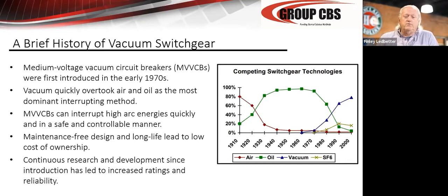Vacuum breakers quickly overtook all the other medias, or, you know, oil, gas, and air. Gas breakers really were a phenomenon in the 80s out of Europe. And the SF6 was thought to be a great way to go about it. They're very complex inside. They have a lot of moving parts inside the pole assemblies, intermediate contacts, mains, and arcing contacts, just like an air breaker, a lot of springs. So they weren't very simple, and they took bigger mechanisms. And then when the EPA decided that the SF6, the sulfur hexafluoride, was a problem, the gas breaker for an intermediate or medium voltage breaker quickly went away. There's a lot of them still out there. We do have to address them from a maintenance standpoint, but you do not see many going into service today in the United States.